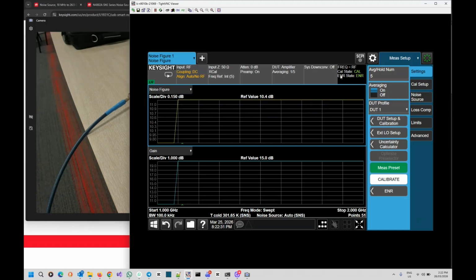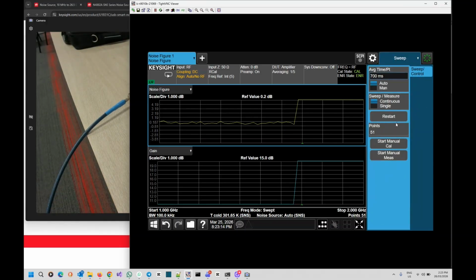Once the calibration is done, you can see the cal state has changed to green color. And the value of this makes more sense right now. It should be about 0-ish. So let's pull that up, and you can see that the fluctuation is much lower if we change the dB per division to something bigger like 1 dB. So it's much better than before the calibrations happened. Let's go to sweep so that we can restart measurements. It's pretty much around that area, which is fine.